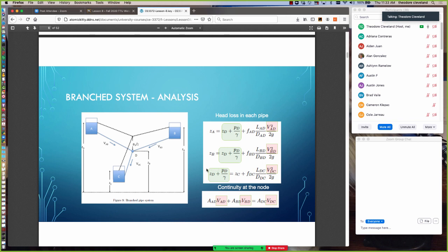We have the total head at node D is equal to the total head at node C plus the head loss going from node D to C. It also depends on the length of the connection, the diameter of the connection, and the as of yet unknown velocity in that pipe. So the green boxes represent the unknown head value, and the red boxes represent the unknown velocities or flow rates.